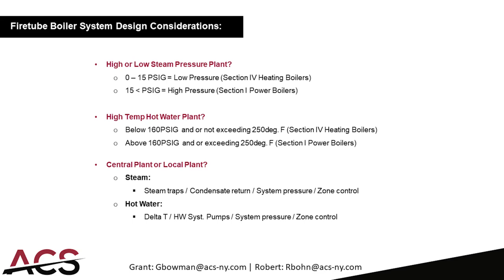Consider whether this is a district utility steam plant or a local heating plant for one or a few buildings, and whether it's a steam or hot water plant. For a steam plant serving several buildings, pay attention to steam traps to collect condensate, condensate return and how it gets back to the condensate receiver and feed water tank, system pressure needed in the header to distribute steam, and zone control valves for a balanced plant.